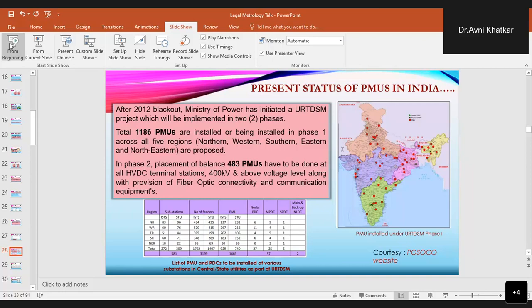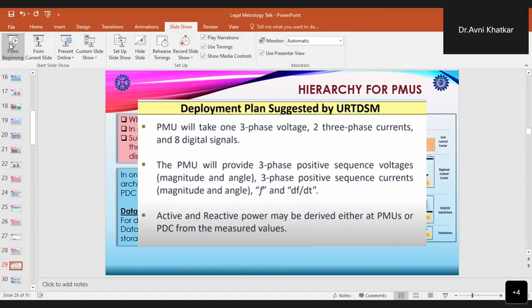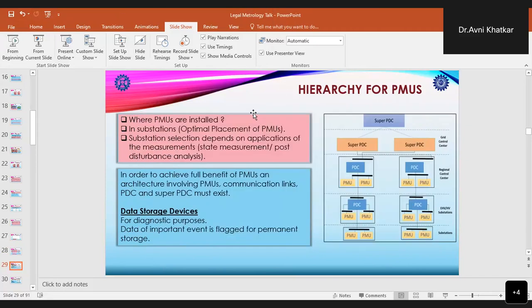In the first phase, around 1186 PMUs were to be installed. And in the second phase, the balance of 483 PMUs had to be installed in the Indian power grid. And then the data from these PMUs, as per the deployment plan strategy, depends on where these PMUs are to be installed. So these PMUs are to be installed as per the optimal placement strategy, that is the substation selection. It will depend on the applications of the measurements, that is, whether it is required for state measurement or post-event analysis. Based on that, the PMUs will be installed in the grid.